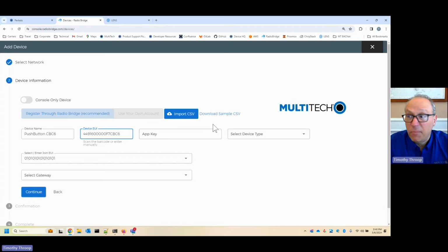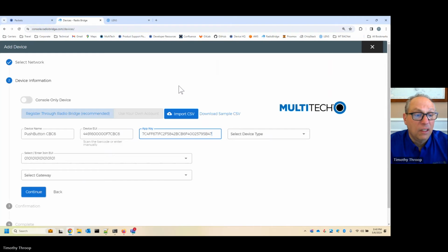Especially with BACnet, because you're not sure exactly what the device is for, having something in the name having to do with its location or purpose is critically important - especially when there are a lot of the same kind, whether contact sensors, temperature sensors, and so forth. It becomes very hard to tell them apart once deployed, so a consistent naming convention is extremely important.